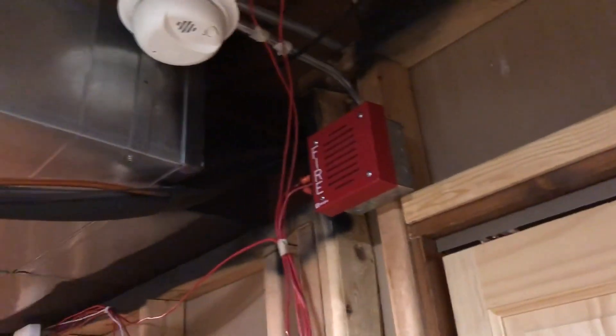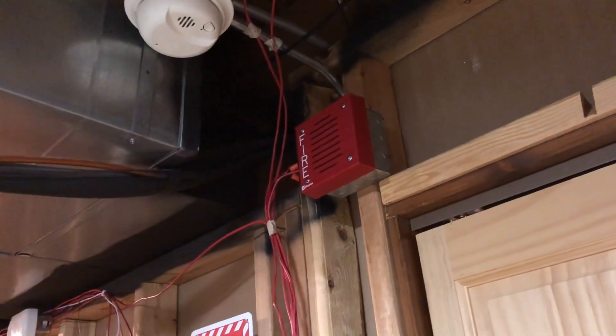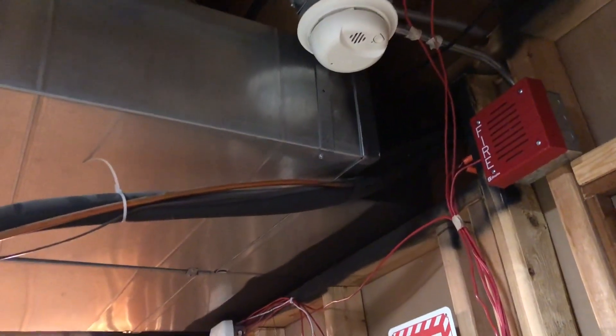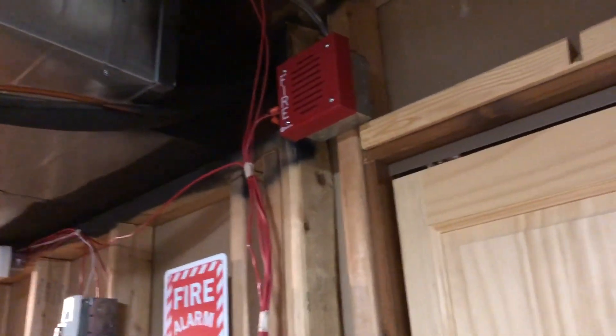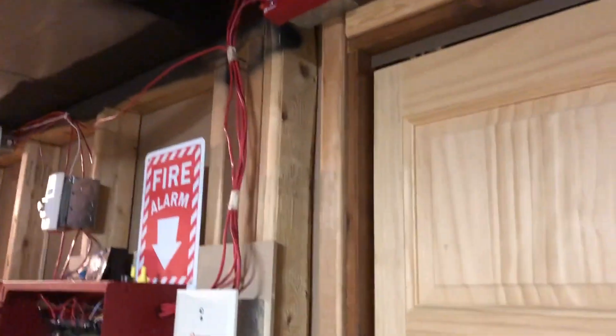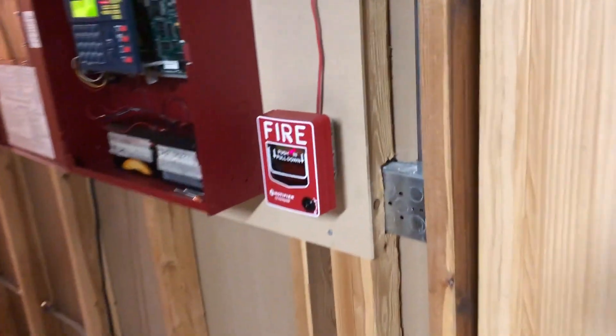I feel like that's an oversight on Fire-Lite's part, and maybe it's just a code thing. But if you ask me, if you're going to be doing a two-stage system — which is really only popular in Canada at this point — it seems like you should be able to jump straight into it if two devices go into alarm. Maybe a smoke detector activates and then a pull station activates — that should go straight into an alarm, but it doesn't. I digress.